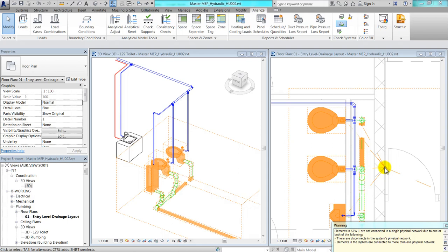They display when any of the following conditions are found. First of all, if a system is not well connected, like it is in our case, the system is physically not sound. Second, if there's a flow-demand configuration mismatch. And the third reason could be a flow direction mismatch.